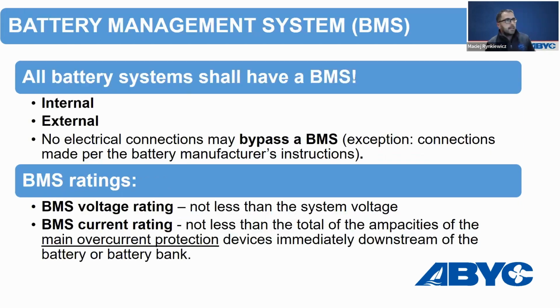Let's start with the BMS. As we said, it's the battery management system intended to disconnect the battery from the system when it reaches one of the limits — high voltage, low voltage, high temperature, or low temperature. That's the basic function of the BMS. It can be internal, like in drop-in batteries inside that plastic box, or external — Victron is a good example of a system using an external battery management system.